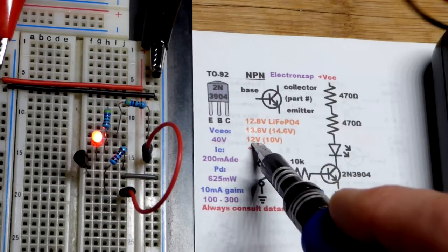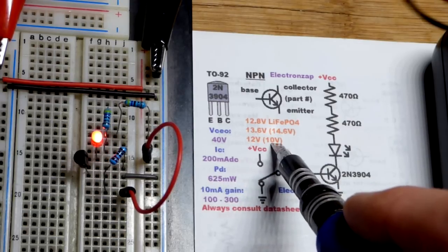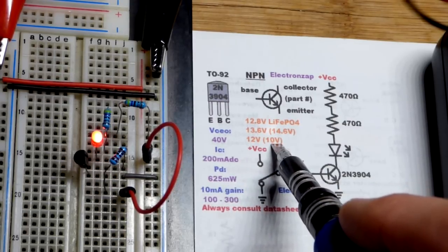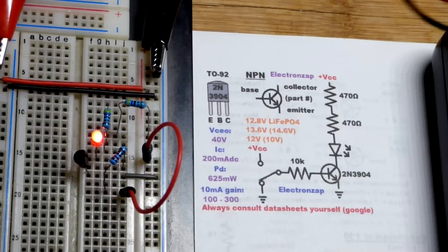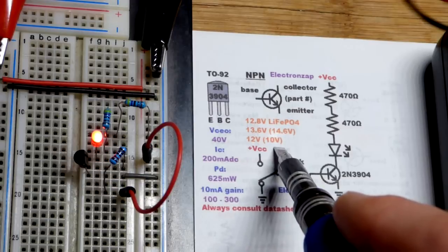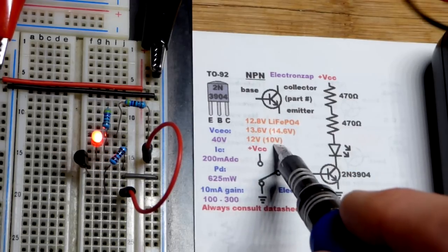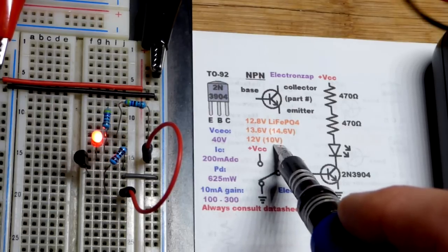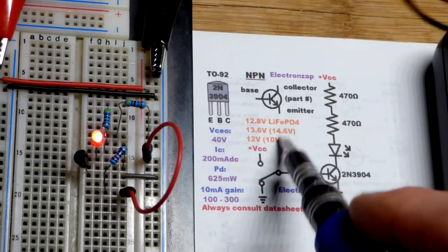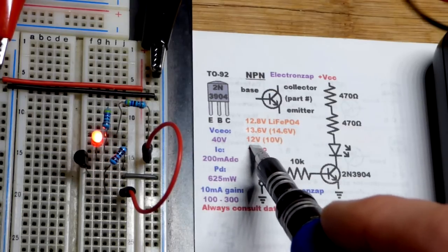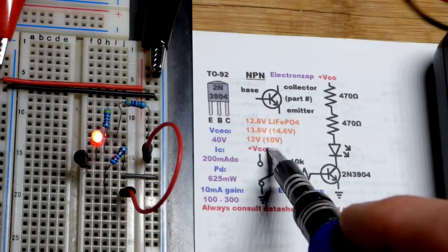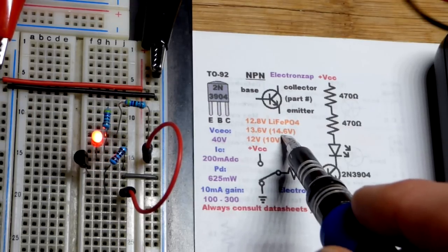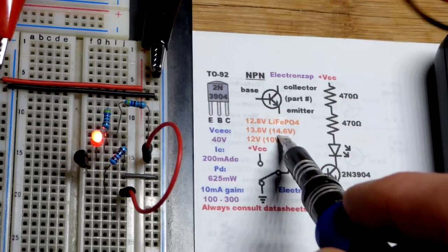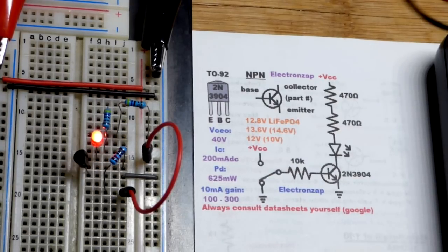12 volts is probably a good spot to stop using it, but you can squeeze out a bit more stored power, going down to 10 volts. Below 10 volts, you start damaging the cells. The individual cells can be discharged to 2.5 volts, and there are 4 of them in a 12 volt lithium iron phosphate battery. So if any of them get to or drop below 2.5 volts, you risk causing damage. They may not always be balanced either, which is another good reason to stop at 12 volts — one cell might be a little lower voltage than the others. Fully charging it often should help balance them, though they don't always stay balanced. Hopefully there's protection circuitry in them to help.